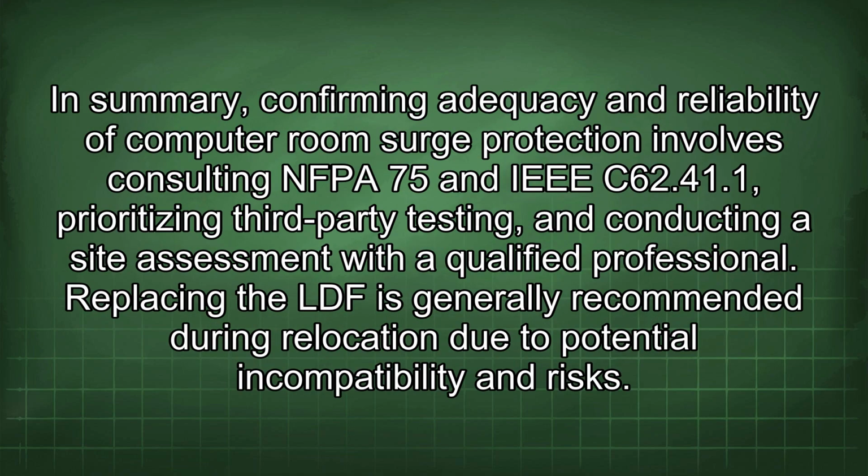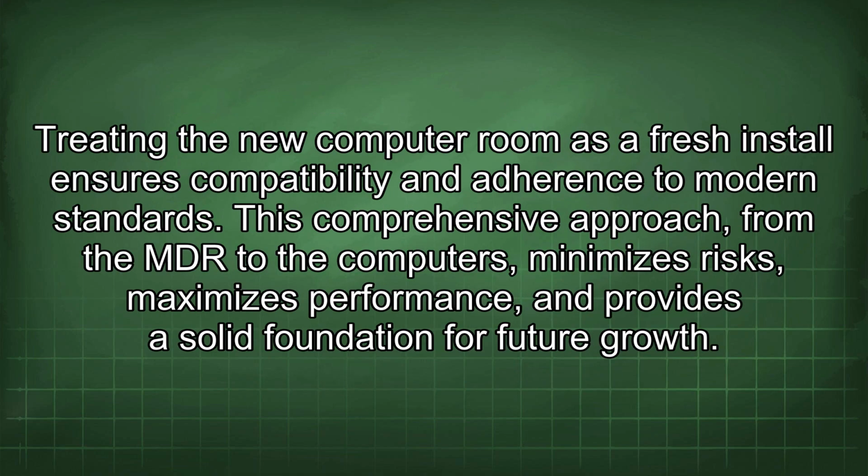In summary, confirming adequacy and reliability of computer room surge protection involves consulting NFPA 75 and IEEE C62.41.1, prioritizing third-party testing, and conducting a site assessment with a qualified professional. Replacing the LDF is generally recommended during relocation due to potential incompatibility and risks. Treating the new computer room as a fresh install ensures compatibility and adherence to modern standards.